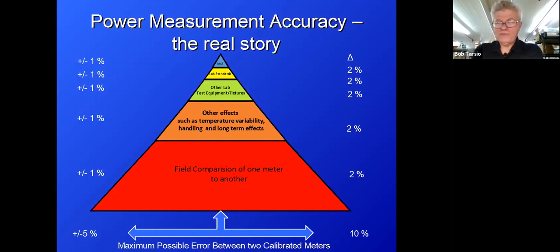Other effects, such as temperature variability, handling, and long-term effects. Well, we've measured our meters under tests from freezing to 150 degrees Fahrenheit. And we know that the typical change in indicated power will be about 1% over that temperature range. And that's normal. Now, most of the time, you're going to keep things in a constant temperature, but we do have to take into account that there is temperature variability.